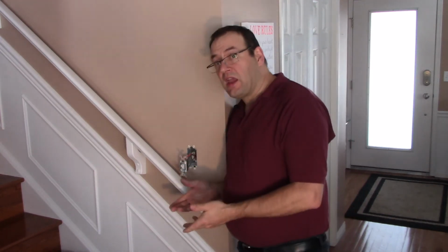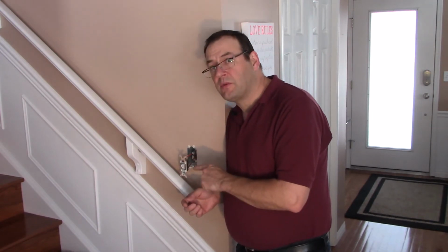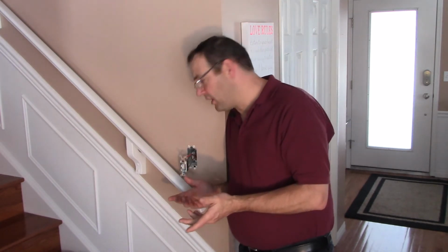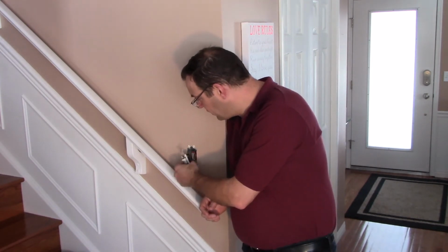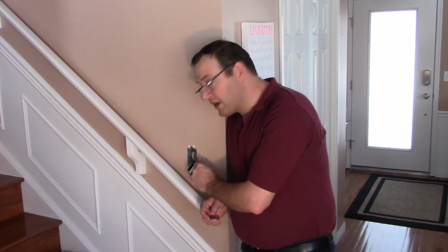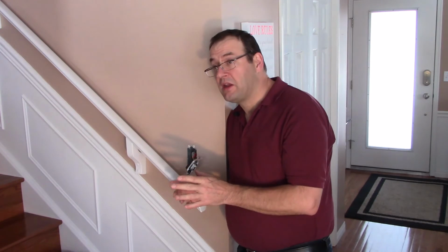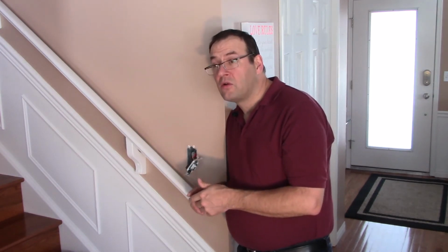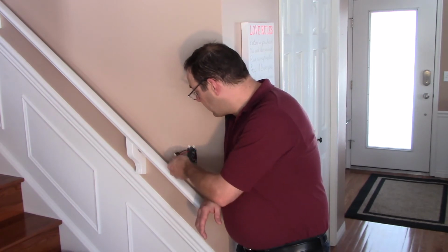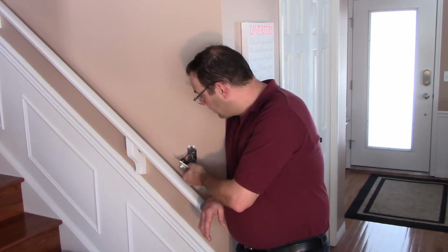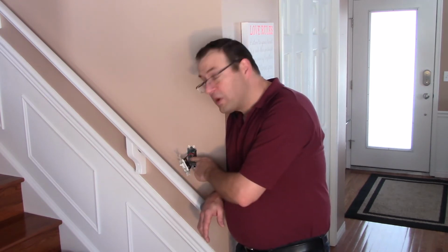Now, in this case, there's two things I want to show you about this. This is a three-way switch. So what did we learn from the last video? It'll have 3 screws, 2 on one side and 1 on the other side. Remember from the last video, there'll be a common screw, which is identified by either being brown, black, or sometimes silver. Well, the other ones will be brass. So here we've got kind of a brown colored screw, and the top 2 are brass, so we have to keep track which wire is on there.